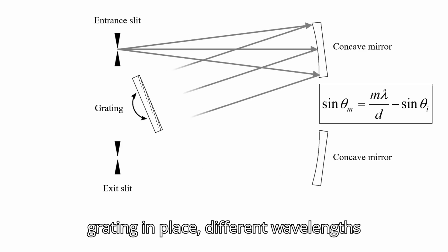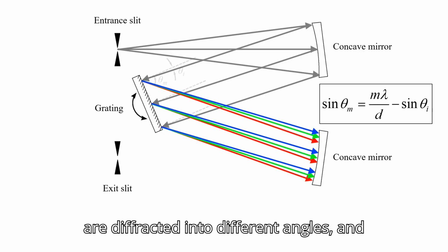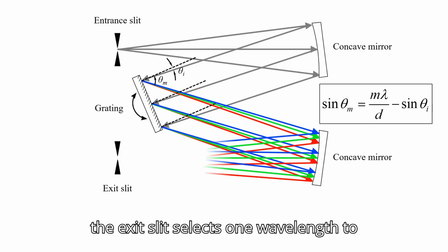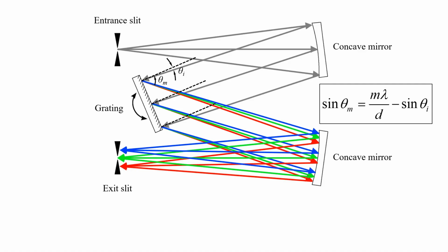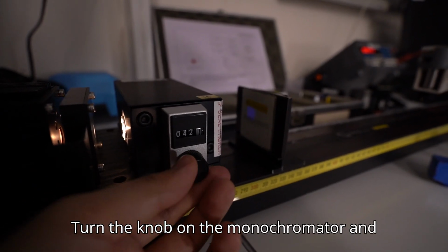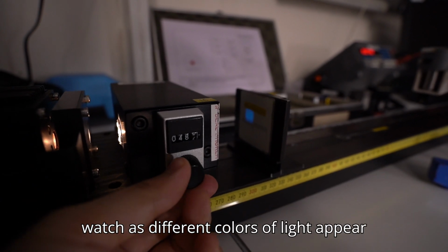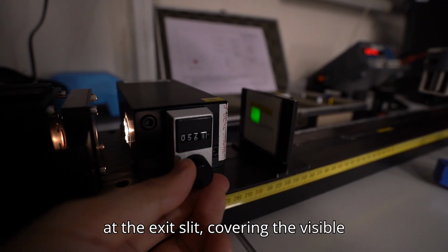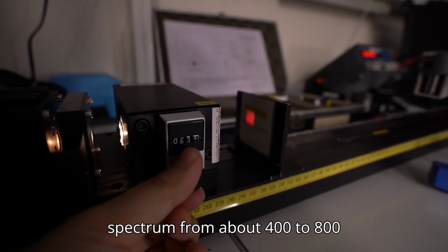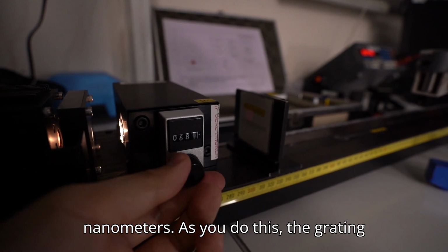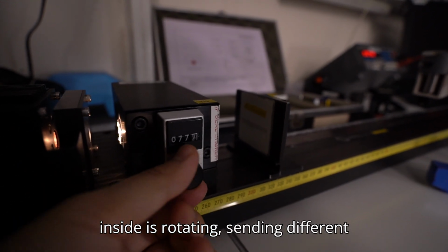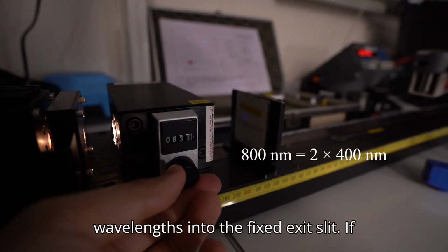With the grating in place, different wavelengths are diffracted into different angles, and the exit slit selects one wavelength to pass through. Turn the knob on the monochromator and watch as different colors of light appear at the exit slit, covering the visible spectrum from about 400 to 800 nanometers. As you do this, the grating inside is rotating, sending different wavelengths into the fixed exit slit.